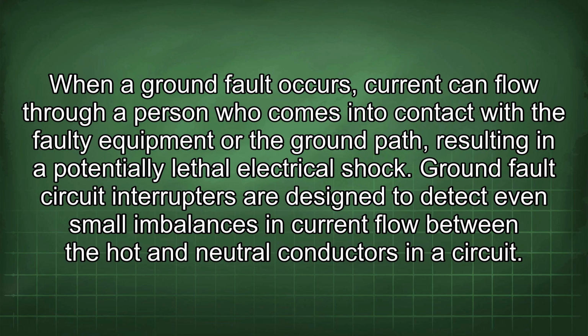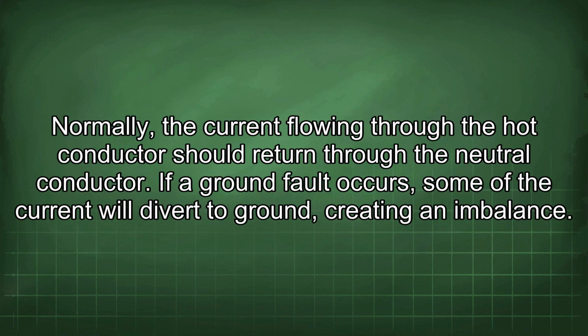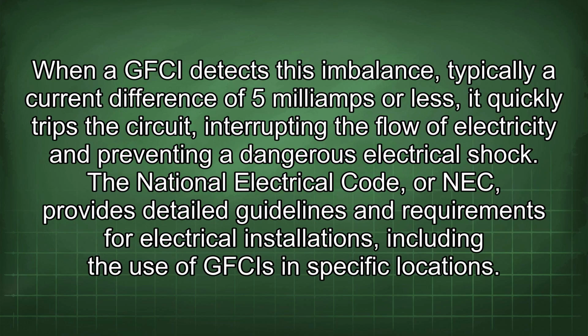Ground fault circuit interrupters are designed to detect even small imbalances in current flow between the hot and neutral conductors in a circuit. Normally, the current flowing through the hot conductor should return through the neutral conductor. If a ground fault occurs, some of the current will divert to ground, creating an imbalance. When a GFCI detects this imbalance, typically a current difference of 5 mA or less, it quickly trips the circuit, interrupting the flow of electricity and preventing a dangerous electrical shock.